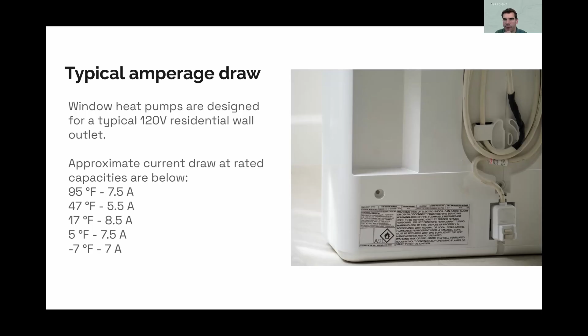Fixed speed induction motors in compressors, which is what's most common in window ACs, have a very spiky startup current. So when a window AC trips the breaker, it's usually that startup current. When you see that current spike on initiation, that is what's killing the breaker. These variable speed systems have two advantages. One, they don't have that startup spike because they're variable speed drives. Two, they're more efficient, so their constant or average current draw is much lower. And so having this low current draw is really important for limiting electrical upgrades as much as possible.